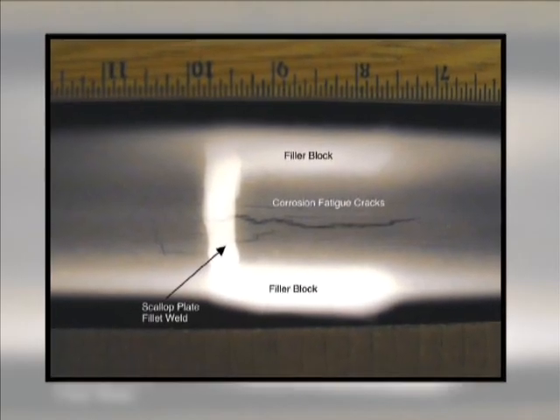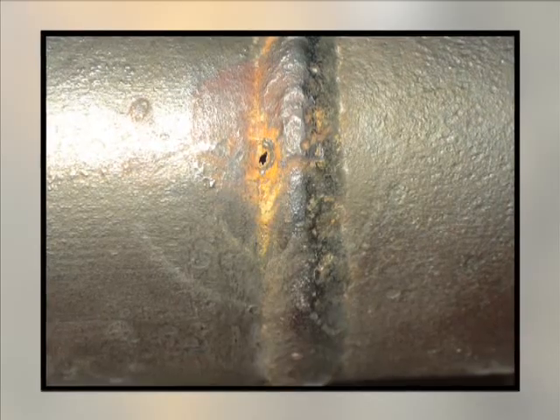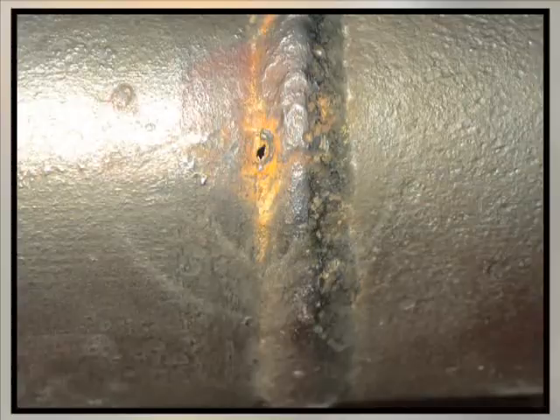These failures usually result in a small crack or pinhole. If these failures are detected soon, and if their consequences can be evaluated, the boiler could continue steaming for some time before having to shut it down. However, the majority of the leaks cause adjacent tubes to rupture, and an urgent shutdown is required.